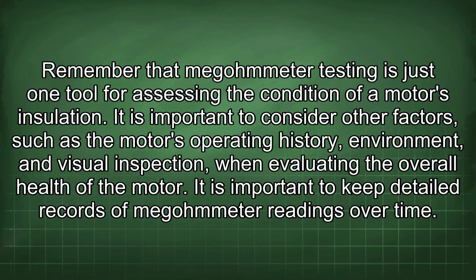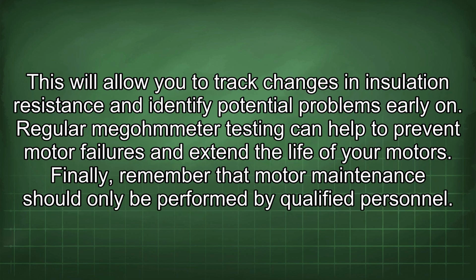Remember that megohmmeter testing is just one tool for assessing the condition of a motor's insulation. It is important to consider other factors such as the motor's operating history, environment, and visual inspection when evaluating the overall health of the motor. It is important to keep detailed records of megohmmeter readings over time. This will allow you to track changes in insulation resistance and identify potential problems early on. Regular megohmmeter testing can help to prevent motor failures and extend the life of your motors.